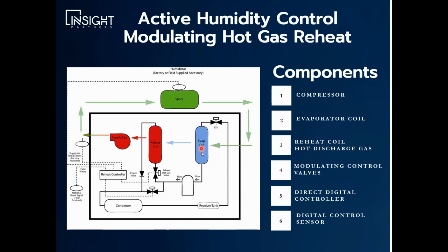The compressor is sucking the gas from the evaporator, compressing it, adding heat and pressure to it, and sending it to the condenser coil, which then rejects the heat to the relatively cool atmosphere. It pushes the refrigerant around to the pressure drop device — the thermal expansion valve — drops the pressure, which allows the refrigerant to absorb the heat from your airflow and boil off, thus cooling the air, and then sends it back to the compressor.